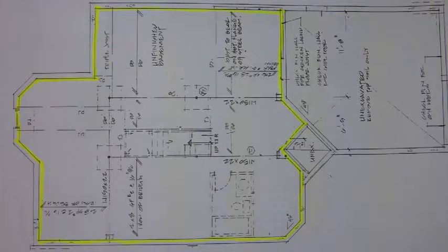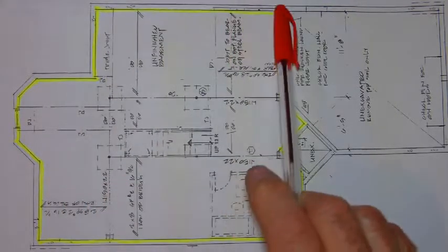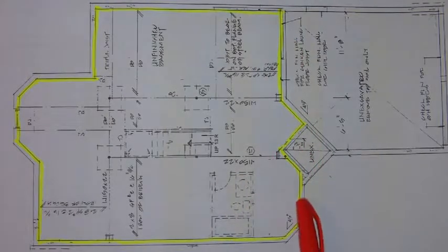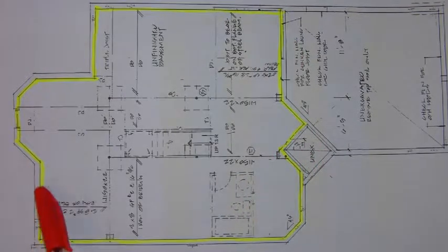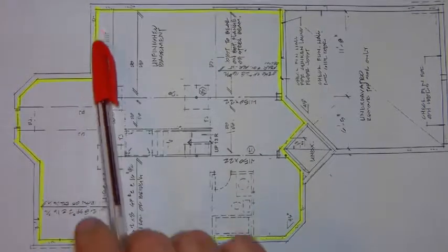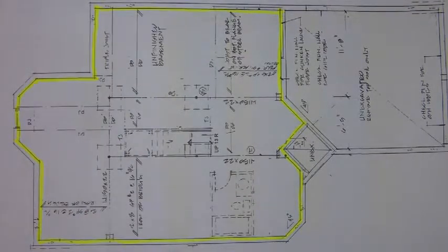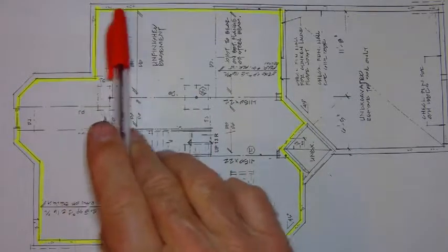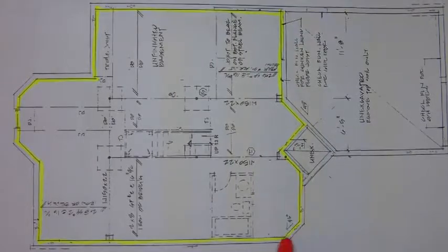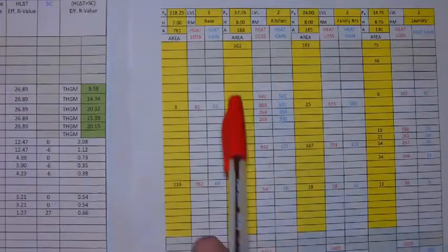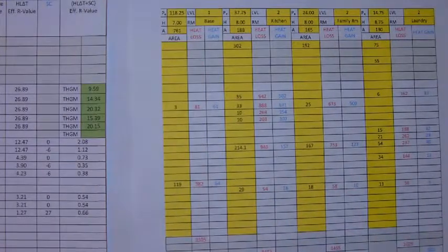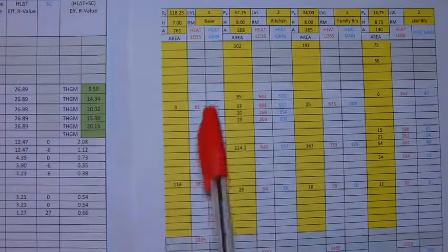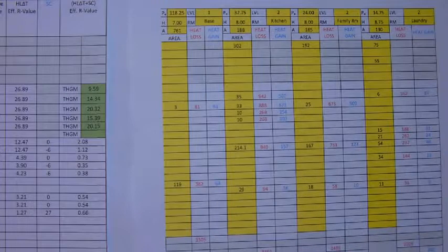When determining the heat loss for the basement, you need to start off by measuring the total distance of exposed wall for the basement. In our in-class example, model 1966, we found that the total distance of exposed wall around the basement came out to 118.25 feet. The height of the basement in general is 7 feet high.